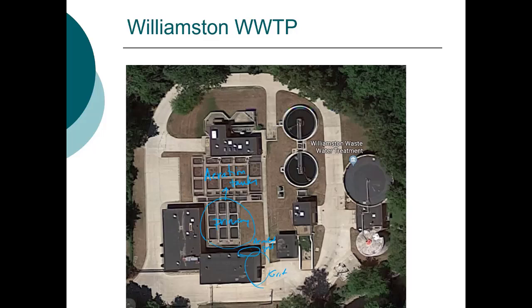So water flows here to the aeration tanks, and then from there to the secondary clarifiers. And then from there to UV, and then it is discharged to the Red Cedar. Just to give you a sense of one treatment plant. These are digesters. The sludge from the secondary clarifiers and from the primary tanks go into the digesters. Actually, it's a two-stage digester. So we'll end there, and happy to answer any questions you may have.